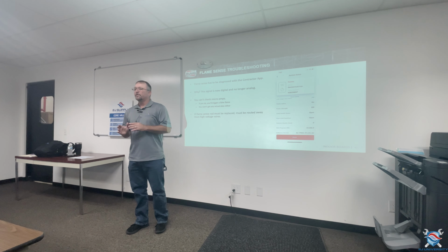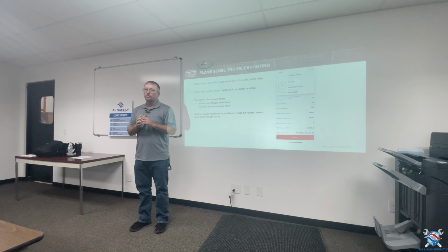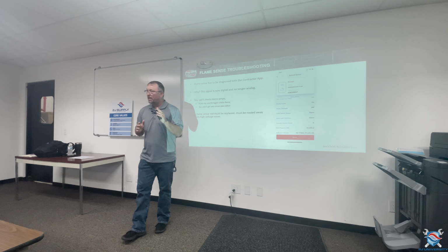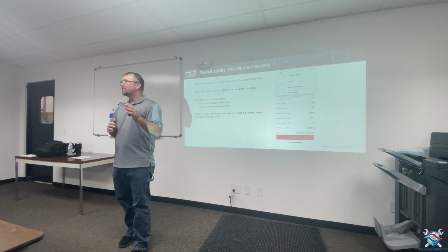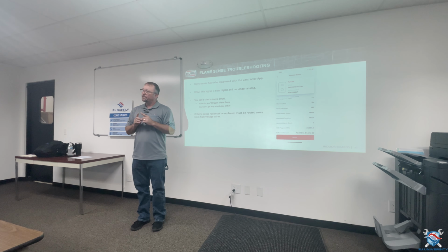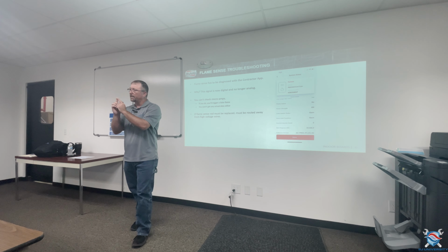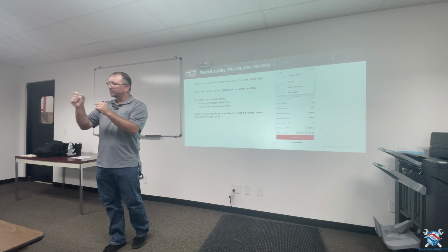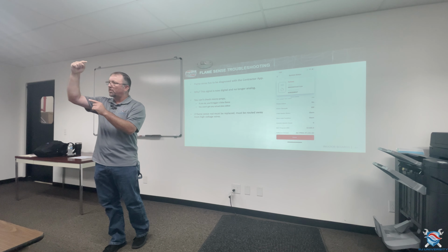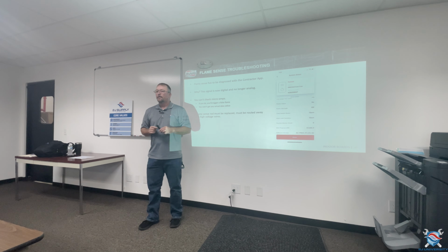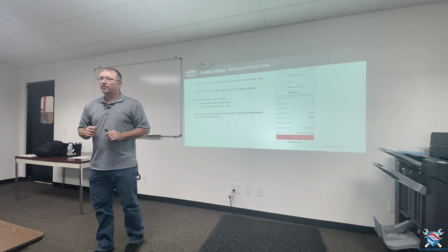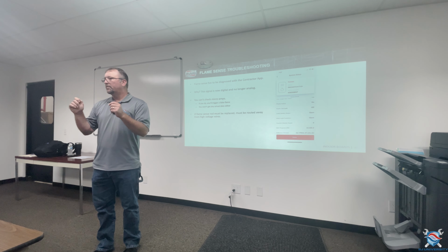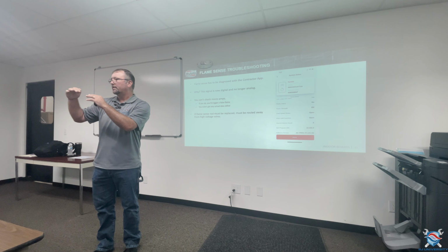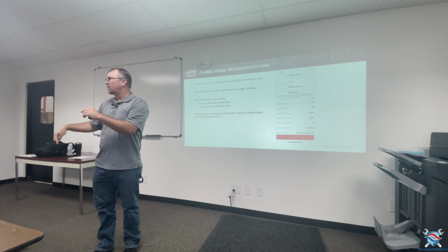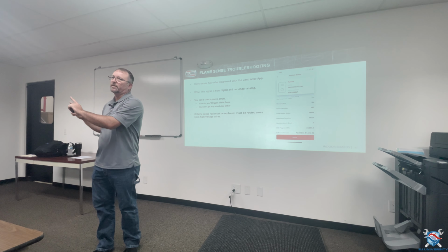What we have done is, originally they were saying that there were bad resistors on the board that was causing it. Not saying that there's not bad resistors, but one thing that they are investigating, because that is a digital signal, is the way those wires are routed. Your flame sensor wire is routed through the cabinet with the spark ignition wire, and they both run together. There's a little grommet in the separation plate, and they go up into the burner box. If you install one of these furnaces, take your ignition wire, separate it from the flame sensor wire, pull it back through that separation plate, and run it back down through the other bundle of wires through the larger hole, and get those at least 2 to 3 inches apart from each other.